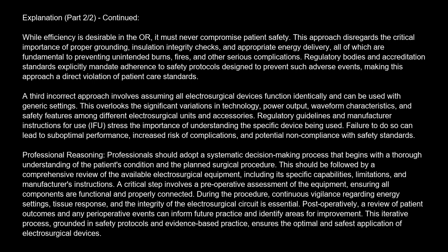A third incorrect approach involves assuming all electrosurgical devices function identically and can be used with generic settings. This overlooks the significant variations in technology, power output, waveform characteristics, and safety features among different electrosurgical units and accessories. Regulatory guidelines and manufacturer instructions for use, IFU, stress the importance of understanding the specific device being used. Failure to do so can lead to suboptimal performance, increased risk of complications, and potential noncompliance with safety standards.